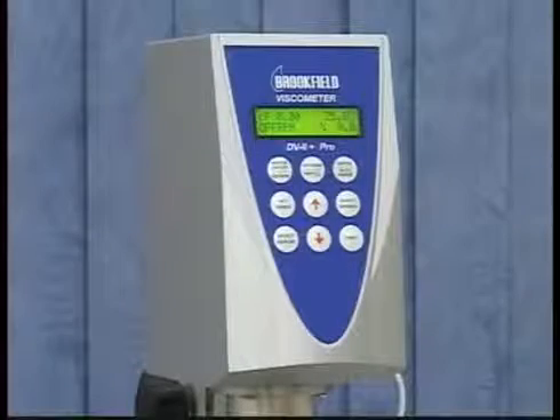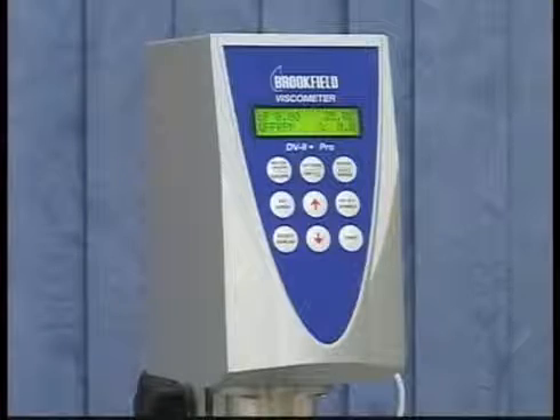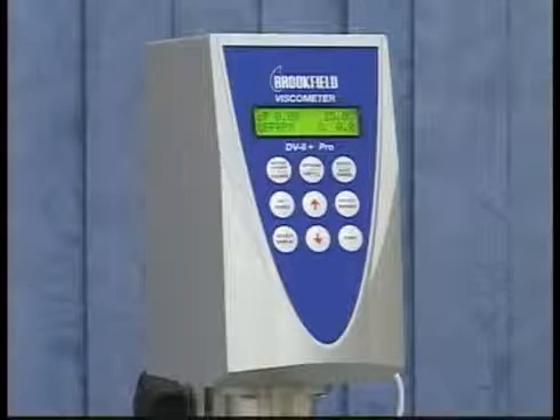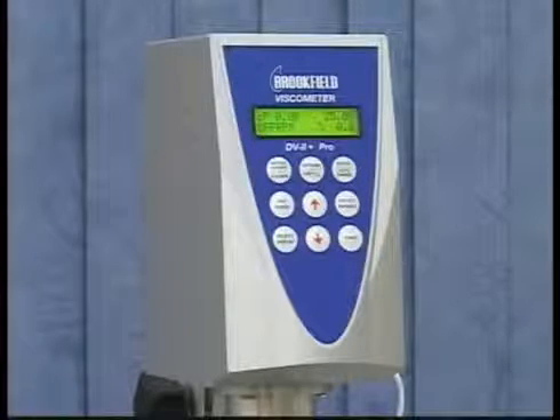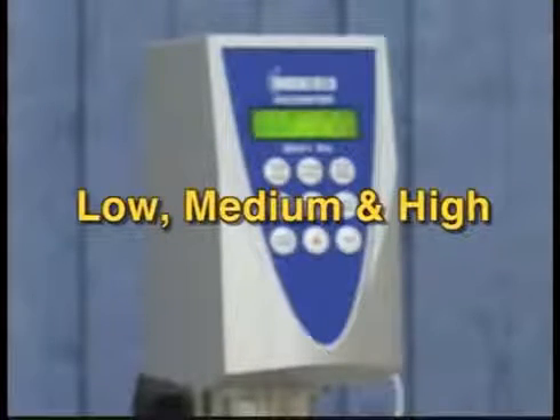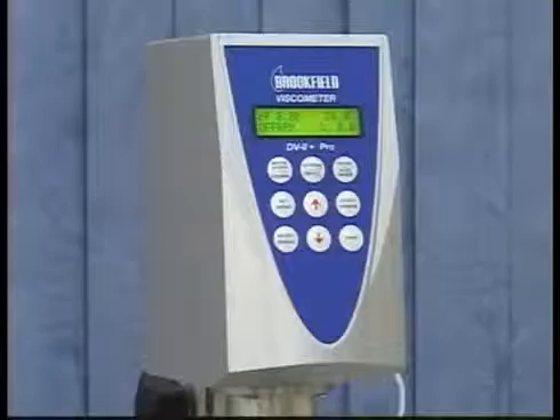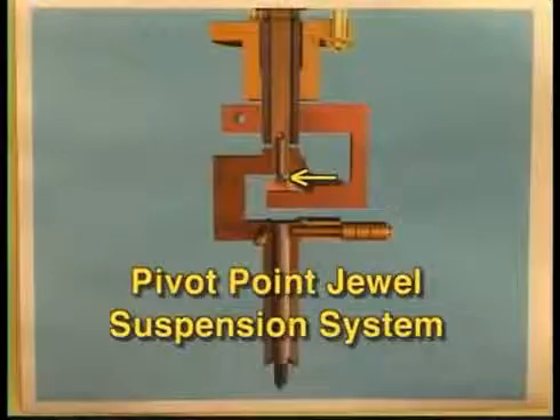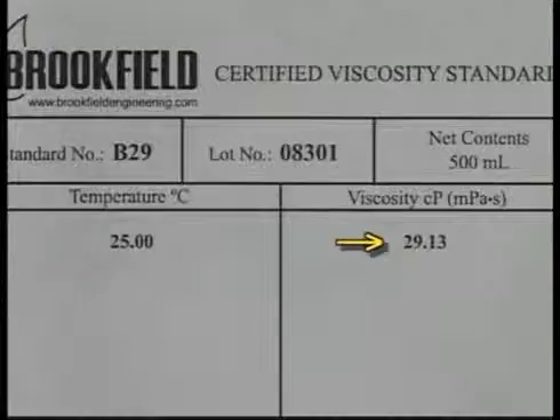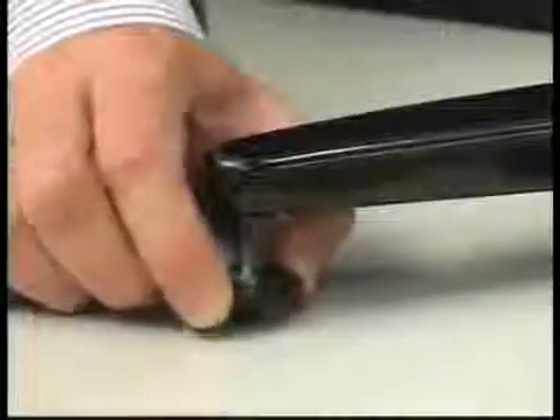The calibration routine checks the linearity of the spring on the instrument by using one fluid at 3 separate speeds to achieve low, medium, and high torque readings. This checks the linearity of the spring and the sensing mechanism of the instrument. Use the actual value of the fluid for the calibration check. Make sure the instrument is level.